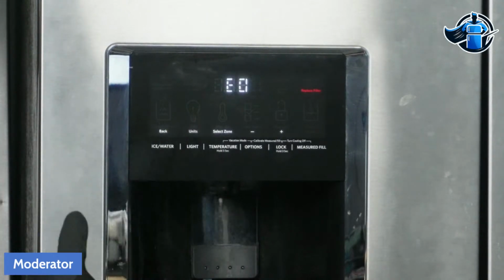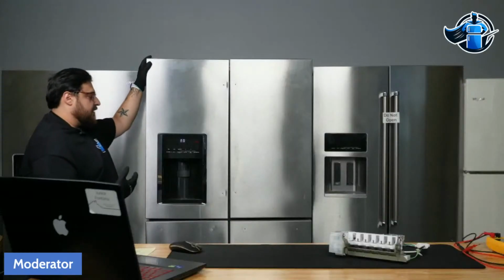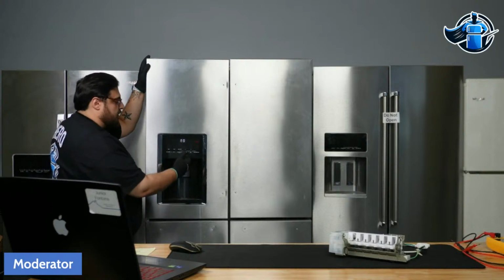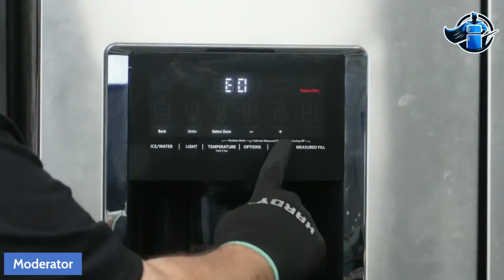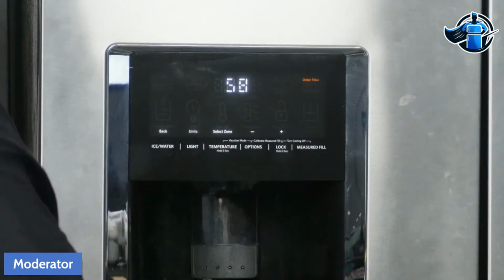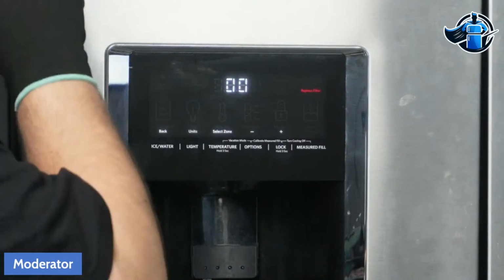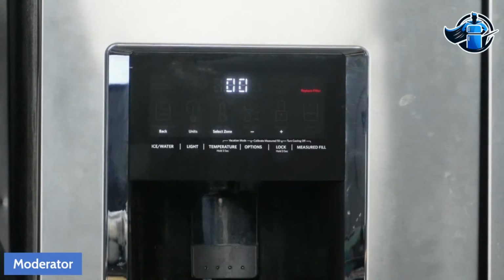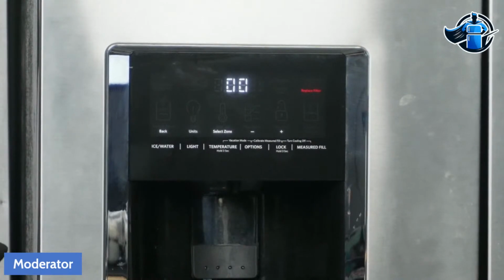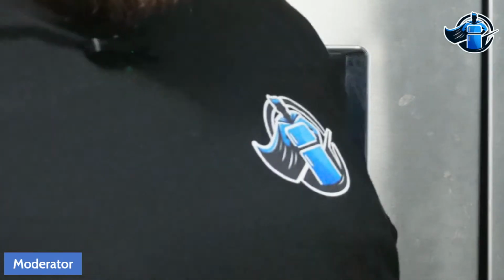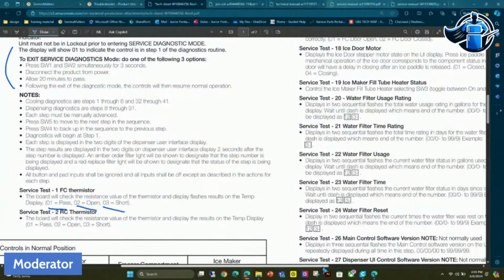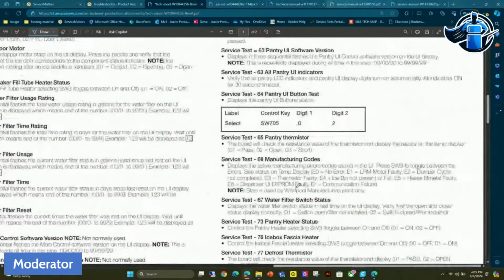Now, this is where most guys will jump up to test 57 and run a harvest cycle. You want to avoid that. You want to go to test 58, where the unit will tell you if it's too warm to run the ice maker. I'm getting a 00. Let's see what that means in our tech sheet. So jumping over here to the computer, let's go to test 58.